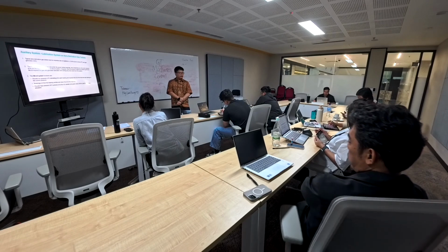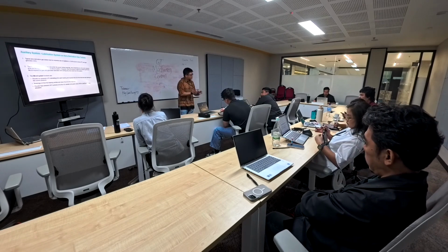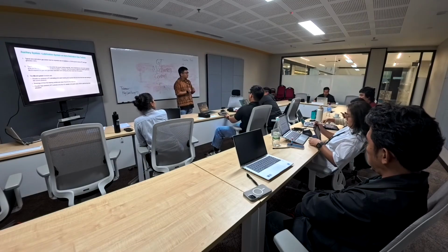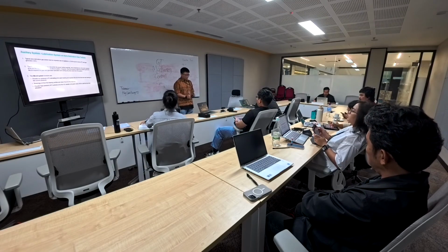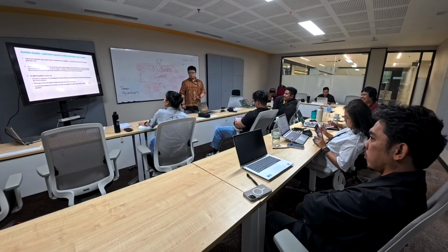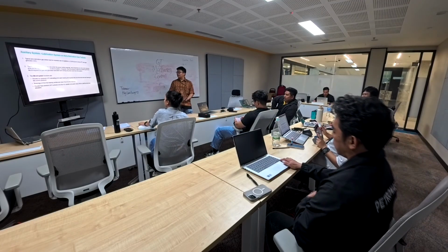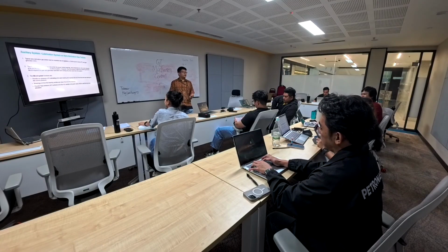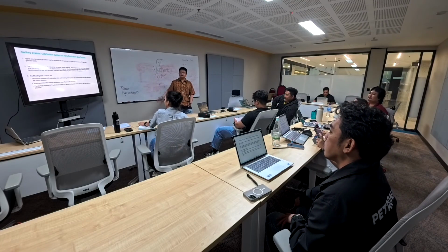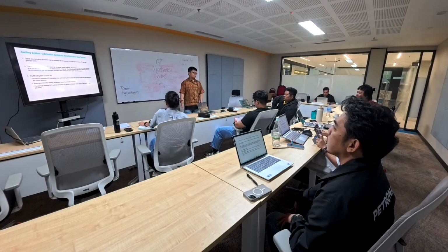Okay, so did I answer your question of why we use synthetic oil? Yeah. Okay, the GG oil or the aeroderivative gas turbine oil system, you have two. One is LP, low pressure, which provides the lubrication to the bearing, and we also have HP. HP is to provide the control oil to the IGV and also some other actuators. But in our case, for our fuel valve, we are not using control oil, we're using an electronic element.